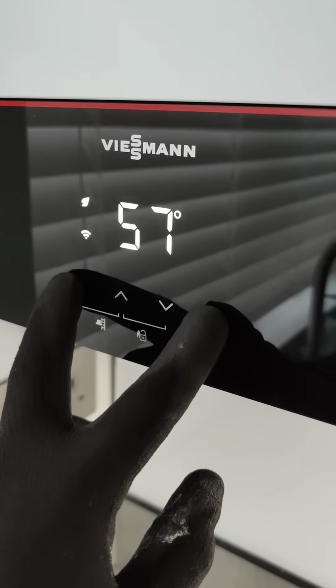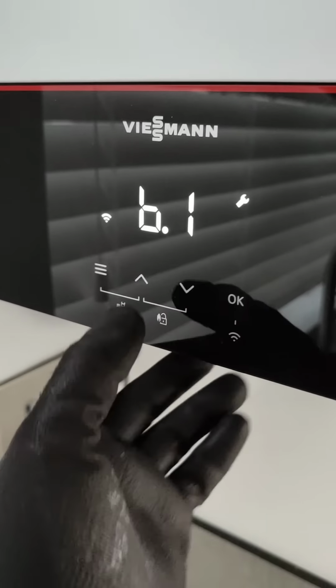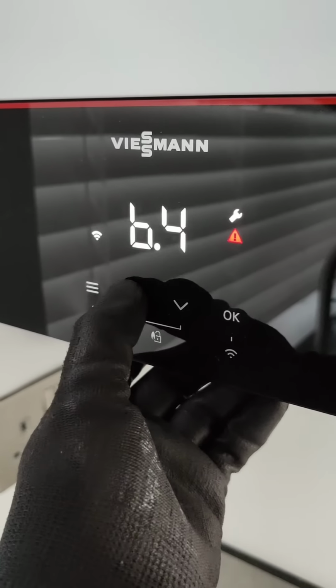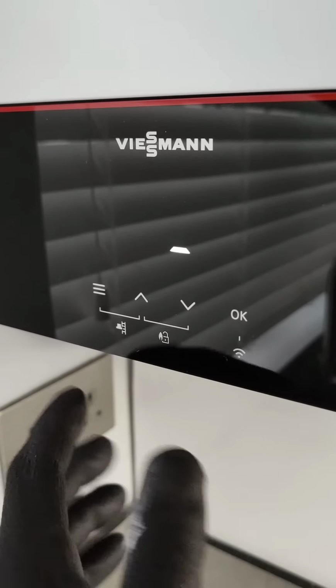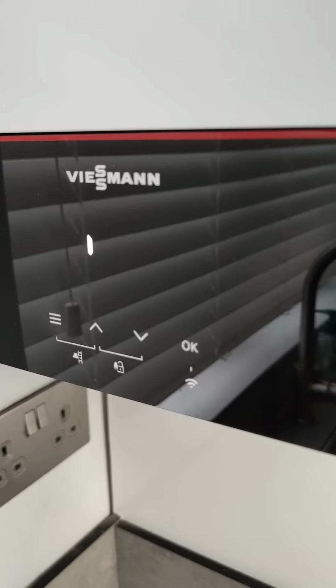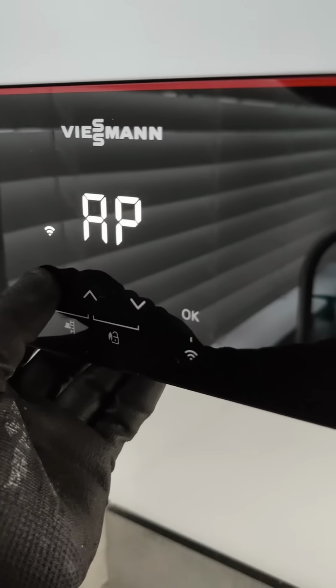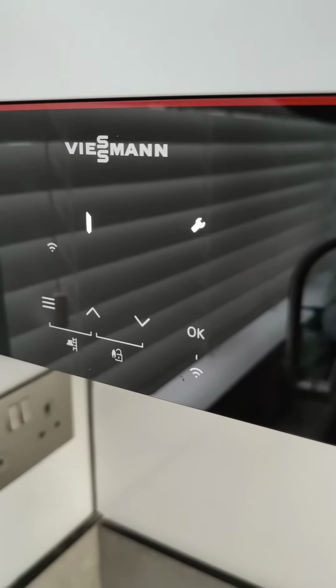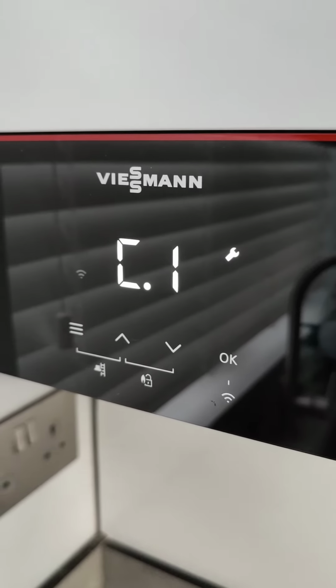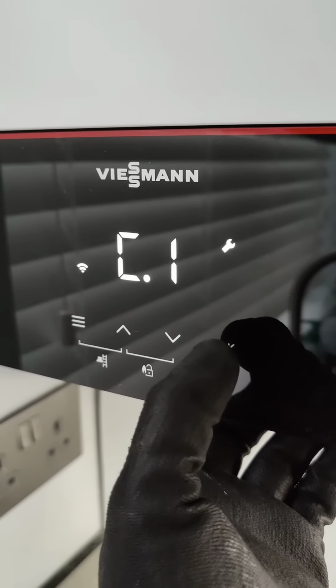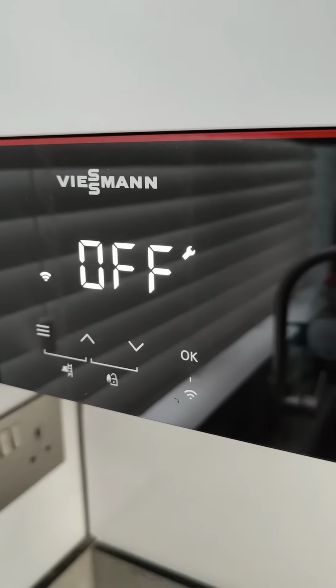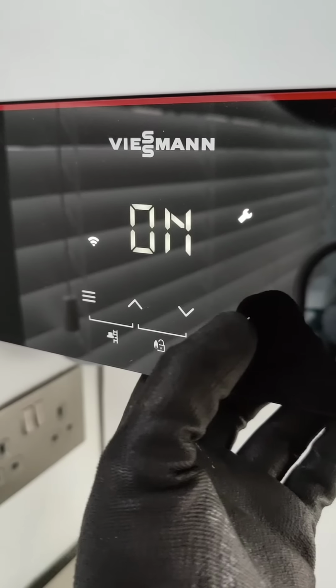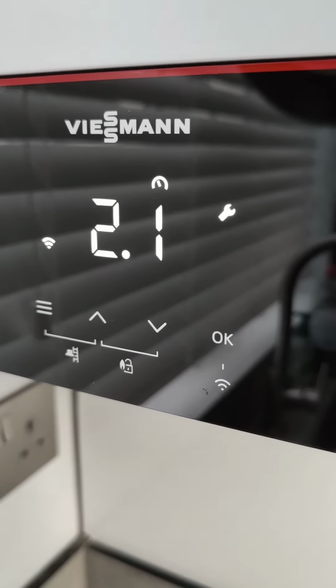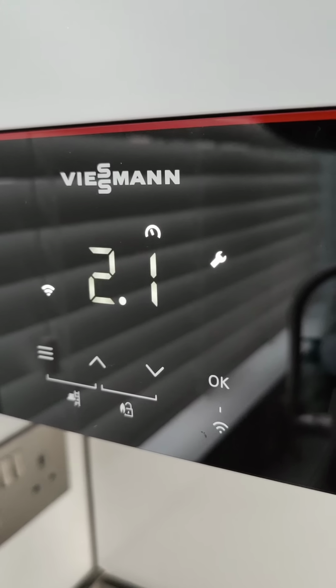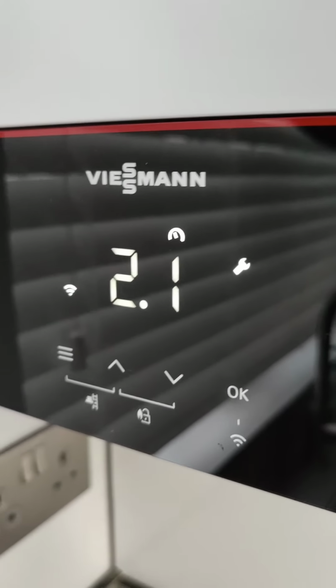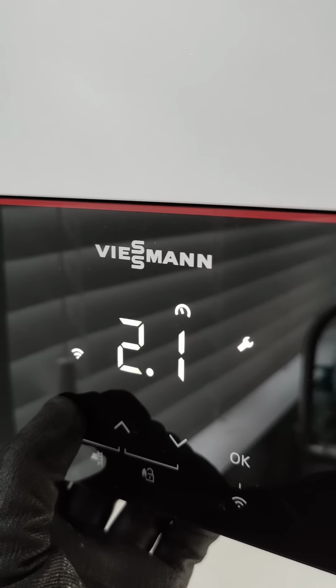We can access the commissioning menu by going to B5. Then if we hold the menu button for 4 seconds, we're going to have the commissioning menu. So C1 is filling, so when we're filling the system we run C1, which will allow the pump to run, so we can cycle between on and off. Now this will show the pressure, and it will also run the pump, and this will run for 20 minutes unless we get out of it by holding the menu button.